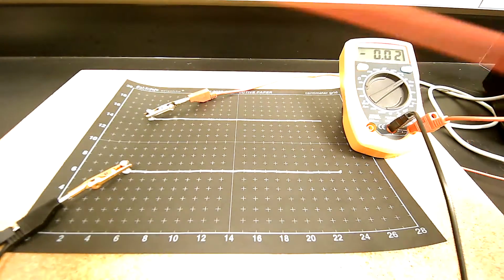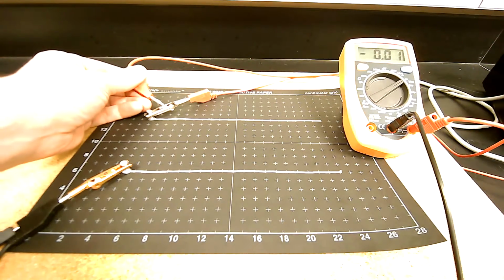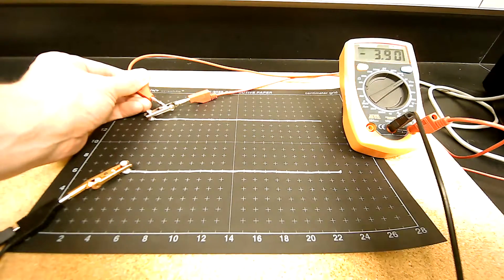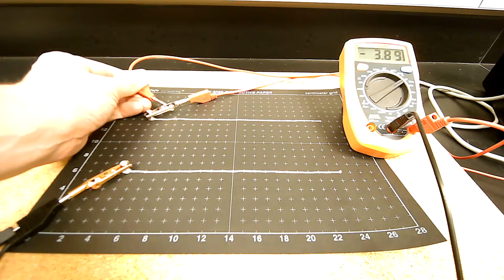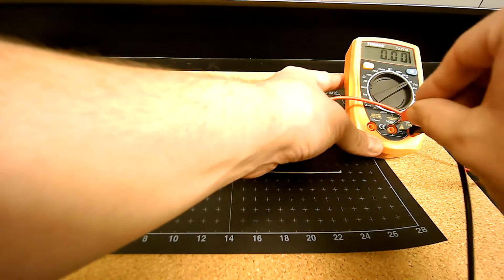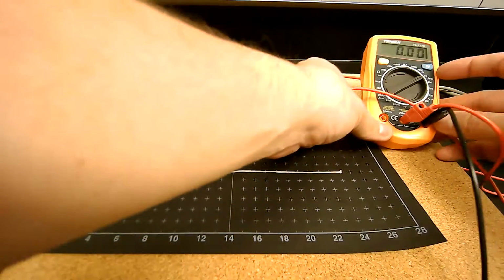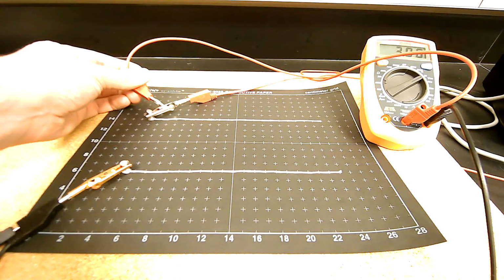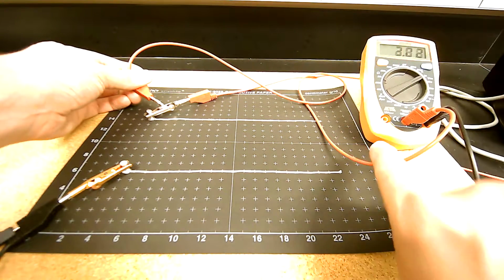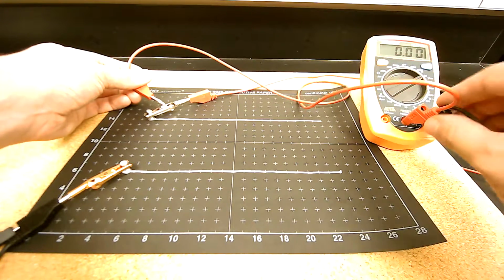Then this probe, the first thing we should do is we should make sure we have 3 volts. If I just touch it on that red probe, we see I have more than 3 volts, 3.9. So that dial on our power supply reads a little bit low. Now I'm just very carefully adjusting that so I can get it as close to 3 as possible. We see I have 3.02. The fact that I have a negative is because I wasn't very careful with how I put these wires in. If the black is in the common side, this says COM, and the red is on the other side, then we'll have positive 3. So all I needed to do is swap it around. Whoops. Positive 3-ish volts. Well, that wire is a little bit loose.